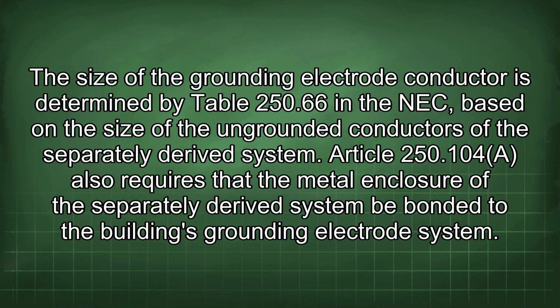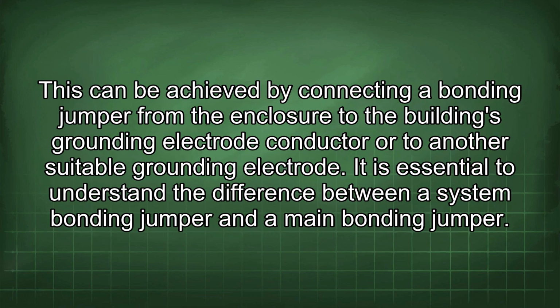Article 250.104 also requires that the metal enclosure of the separately derived system be bonded to the building's grounding electrode system. This can be achieved by connecting a bonding jumper from the enclosure to the building's grounding electrode conductor or to another suitable grounding electrode.